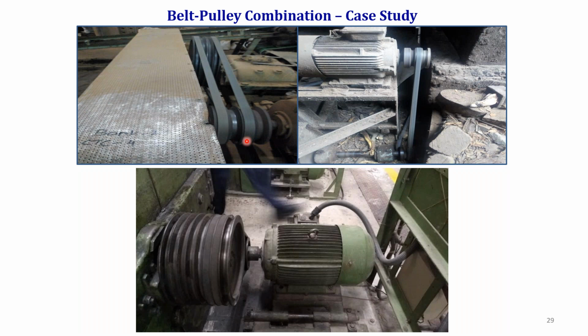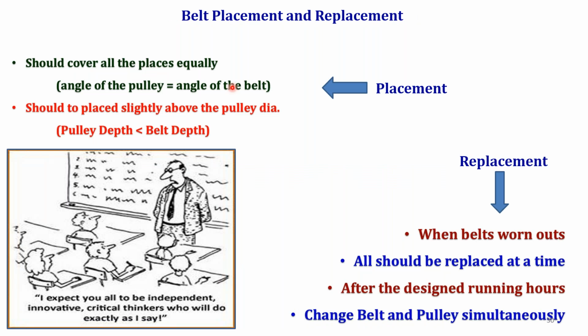And sometimes you can have different types of pulleys not matching between the motor and machines, even when they are running in different configurations. That also will lead to a high amount of power consumption, because the weight on the machine pulley and motor pulley will always be on the motor side. So automatically, an excess amount of load will be applied, and the motor will draw a huge amount of current to drive this. Now, some best practices are available, and most of the time we will always look into the best operating practices.